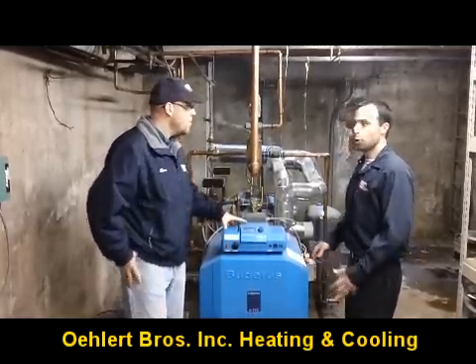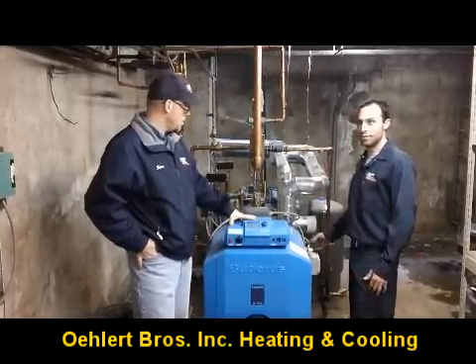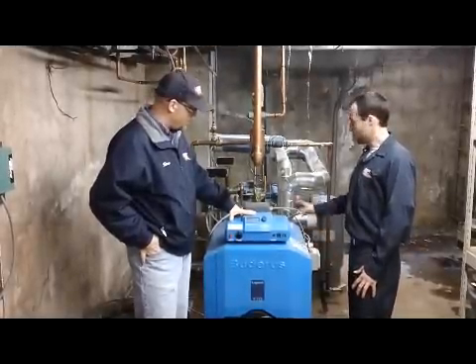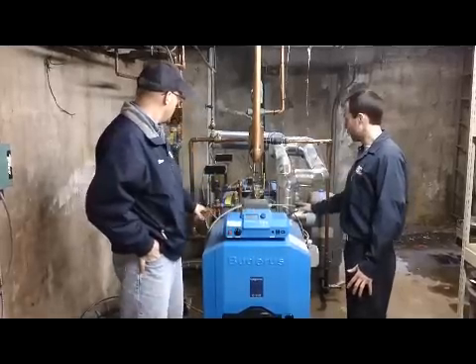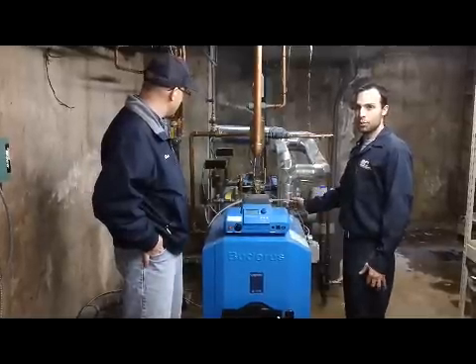The reason is a bigger boiler runs off a two-gallon-per-hour nozzle or more to heat a whole building, getting up to 180 degrees and burning massive amounts of oil. With two smaller boilers with smaller nozzles and a staging control, you've got a primary boiler and a secondary boiler. The primary runs most of the time to keep the water warm, and on a colder day, it'll fire up the second one.